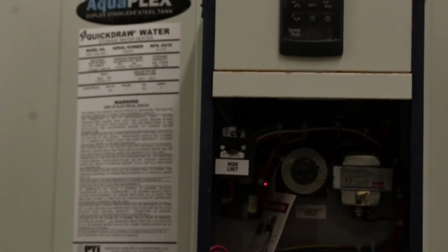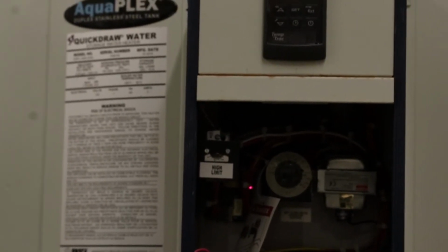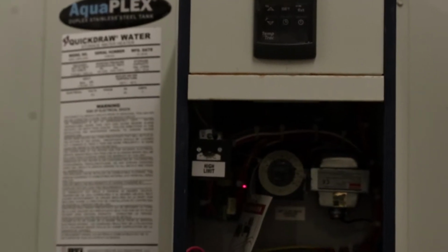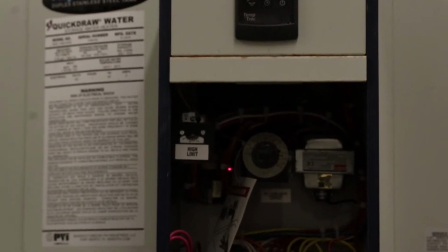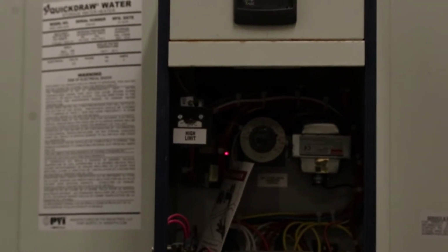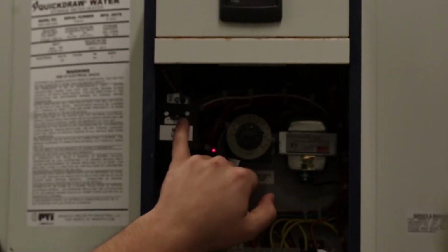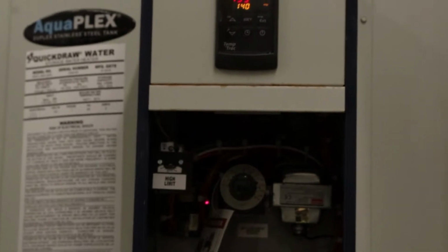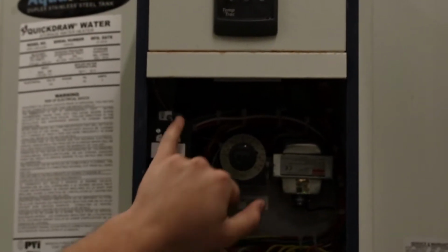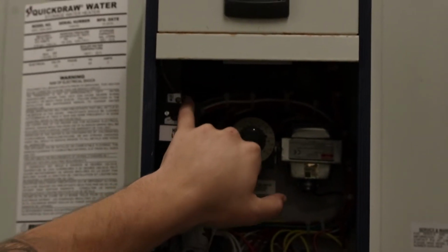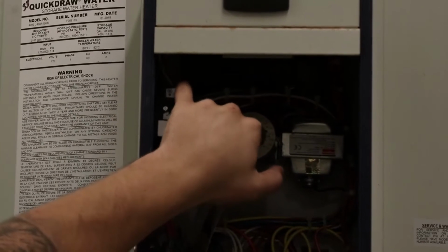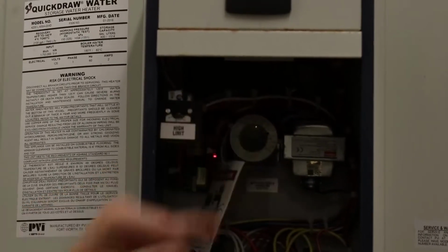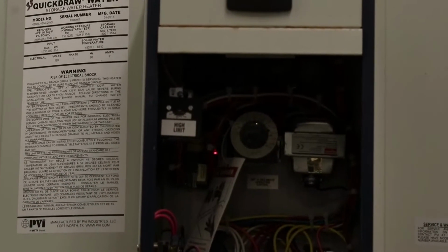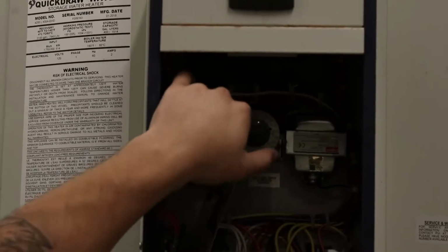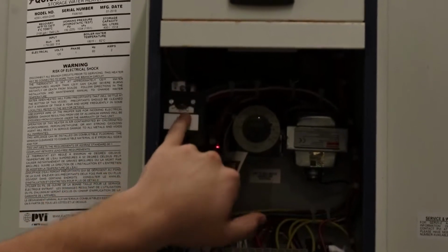If there's any type of malfunction of any of the controls or components that will cause this water heater to overheat the water in the tank, then this control will trip. It's a manual reset type, so it will not allow the water heater to operate again until someone comes in and presses this button. It's a green button there. Right now there's no resistance on the button. It doesn't click because the control is not tripped. If it is tripped, you'll press this button, you'll get a click, and the control will reset.